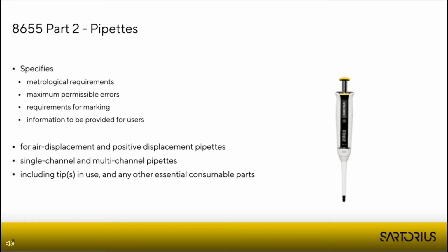Maximum permissible errors, that's quite clear. You have systematic error and random error and maximum limits that the devices must be able to fulfill. What I want to highlight here is that it's always a pipette and tip combination that such limits are given to.